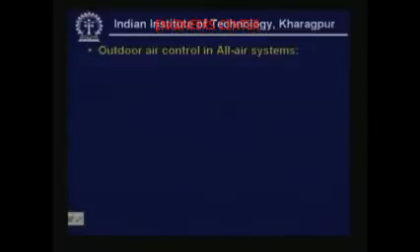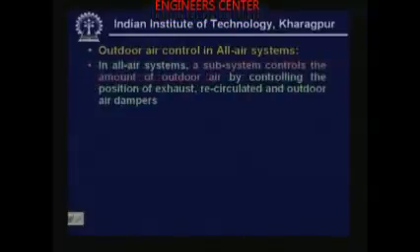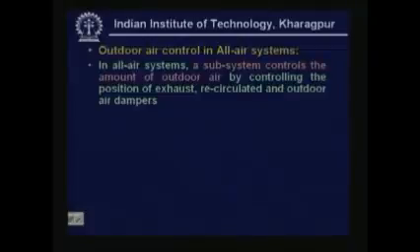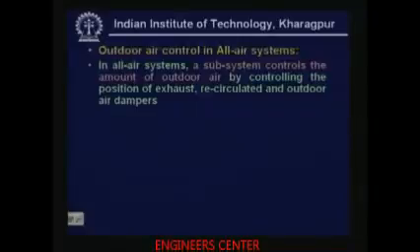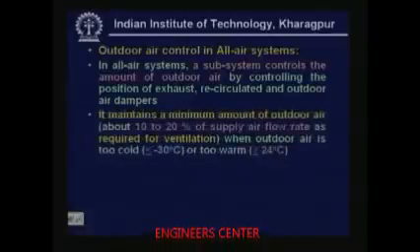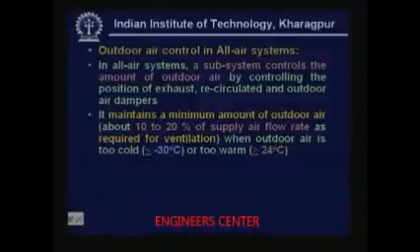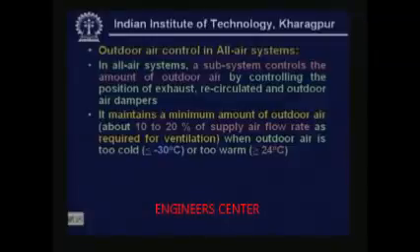Now let us look at outdoor air control in all air systems, which refers to both single duct as well as dual duct systems. In all air systems, a subsystem controls the amount of outdoor air by controlling the position of exhaust, recirculated, and outdoor air dampers. This system maintains a minimum amount of outdoor air — about 10 to 20 percent of supply air flow rate — as required for ventilation when the outdoor air is too cold or too warm.